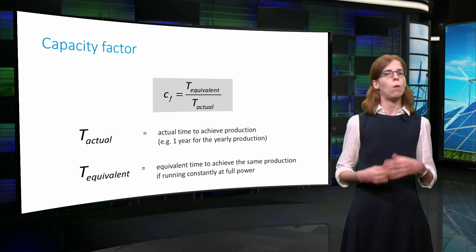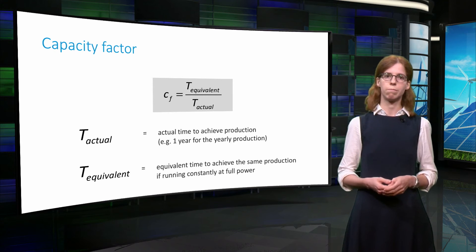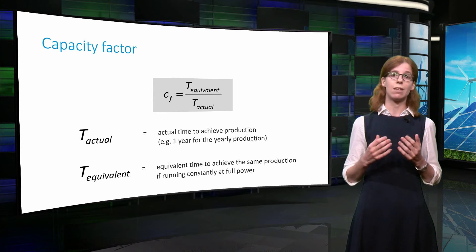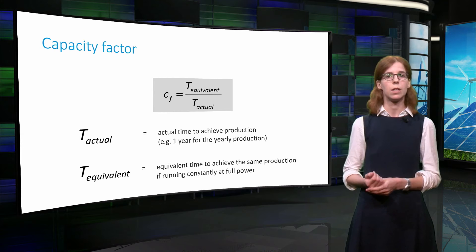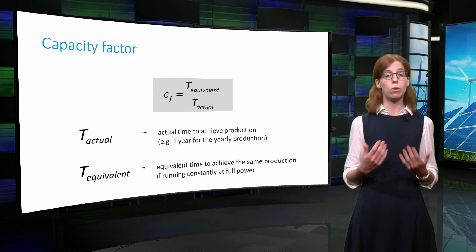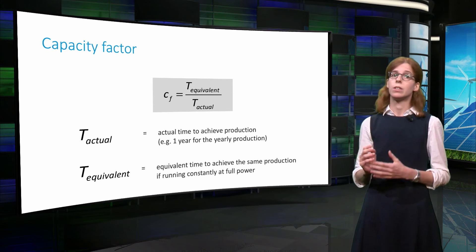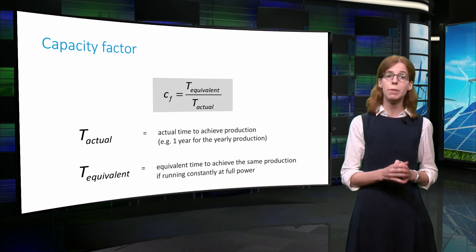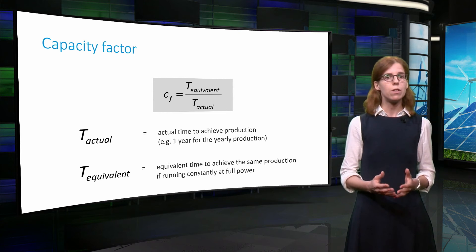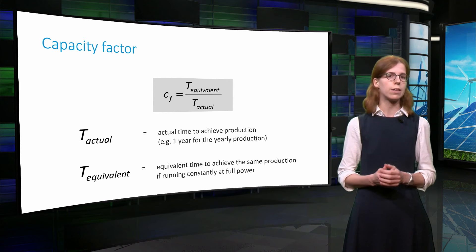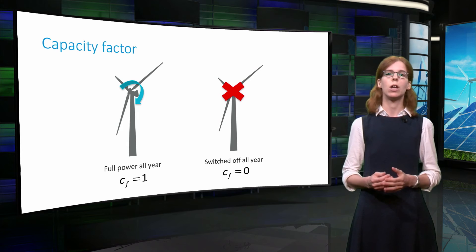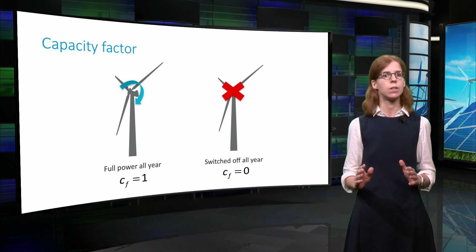Before concluding this video, I would like to talk about an important concept used in energy production — the capacity factor. The capacity factor indicates the percentage of time a system runs at full power over a reference period of time. In this formula, the actual time is the reference time to achieve the given production — for example, one year, if we are considering the yearly production. The equivalent, on the other hand, is the time needed to achieve the same yearly production if the wind turbine was running all the time at full power. By definition, the equivalent is always smaller than the actual, so that the capacity factor is always smaller than unity. In the ideal case of a wind turbine running all year at full power without interruption, the capacity factor equals 1.